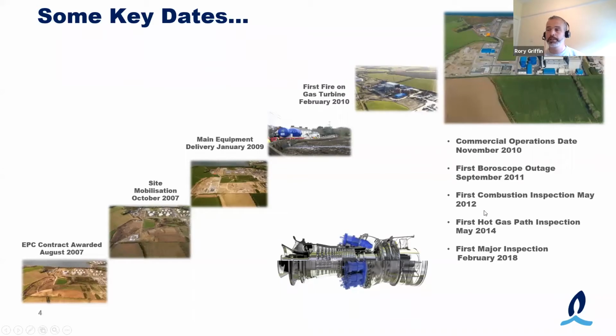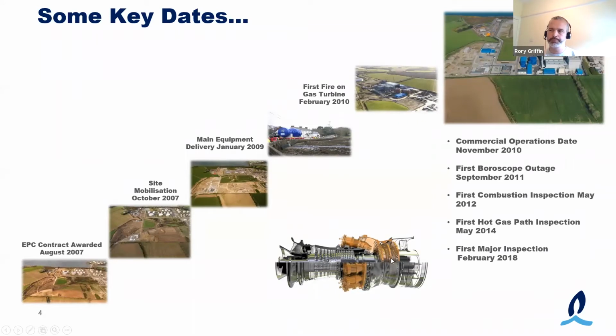So the following year, in May 2012, we went into a combustion inspection. Here you have 18 combustion cans arranged equally around the unit, and at the time every 12,000 hours on the machine you would change these out. And if we go then to May 2014, the first hot gas path inspection, so this interval will be 24,000 hours on the machine, and in this outage the combustion cans were changed out, but also the blades on the gas turbine, and also then there was an inspection on the compressor blades.